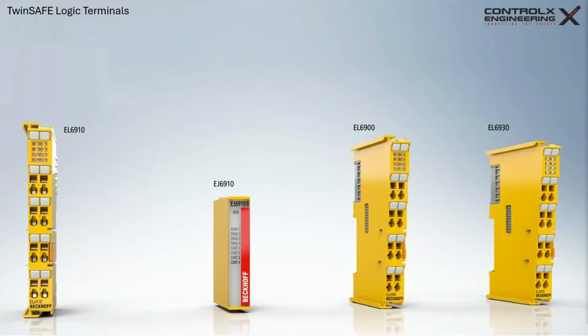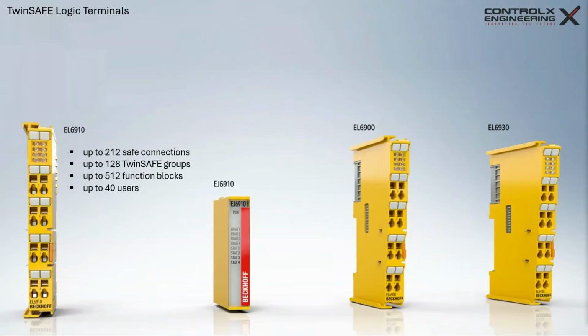These terminals use certified function blocks to process safe inputs and generate safe outputs, and they communicate using FSoE over the EtherCAT network. They're designed to meet high safety levels, including SIL 3 and PLE, depending on the application. Some of the most commonly used logic terminals are shown on the screen. I've personally executed a lot of safety projects using the EL6900 and EL6910 terminals. Some of the features of the EL6910 are listed here.